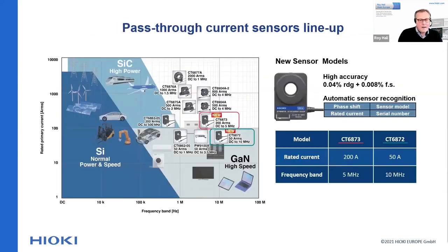Here you see the overview of the pass-through current sensors. This type of current sensor provides the highest accuracy and bandwidth. I'd like to point out especially the CT6872 and 6873, which both have an accuracy of 0.04% of the reading and 0.008% of the full scale. This is very, very good.